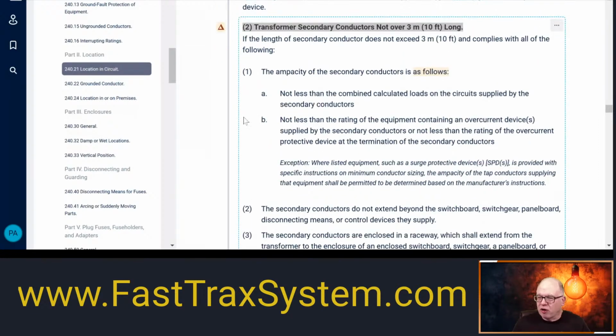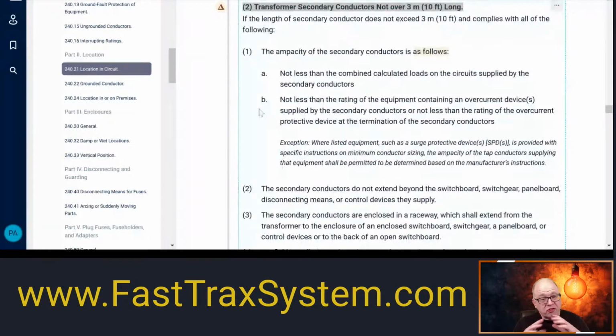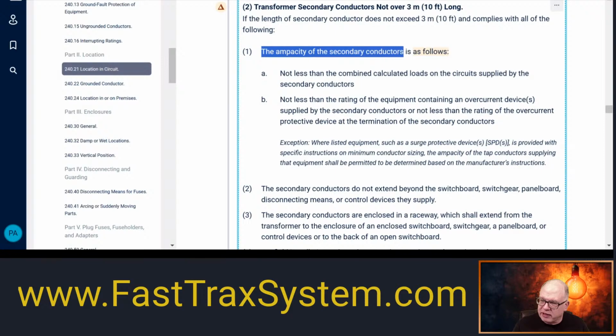All right, so let's talk about it. The first thing we're going to talk about is those secondary conductors. Again, remember, in your mind, picture the transformer, the load side of the transformer, the output of the transformer, whatever you want to call it, going out of the transformer and into an enclosure, let's say, with a breaker, okay? So it says, the ampacity of the secondary conductor is as follows, okay?